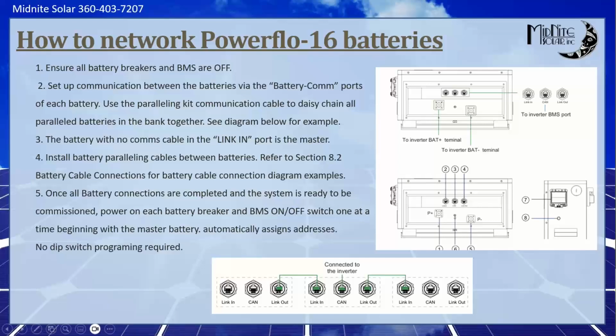So communications on the PF16 is the same, but a little bit different. One thing I've left in here intentionally because it's in the manual, and we're working to get that manual corrected. Just like I said on the other battery: link in, link out. The battery with an empty link in port is the master battery and must have the closed loop CAN cable. As shown in the manual, if you wired this up, you would not get closed loop communication with your inverter. This cable is incorrectly drawn, and we're fixing that as we speak.